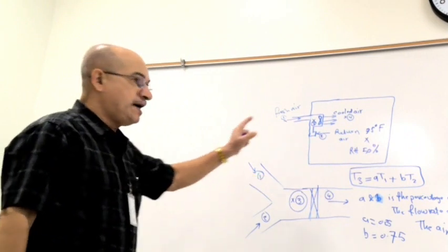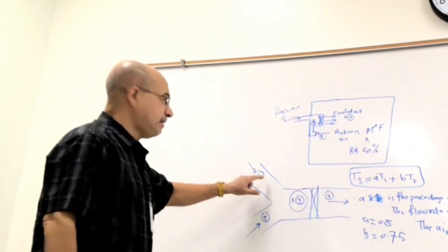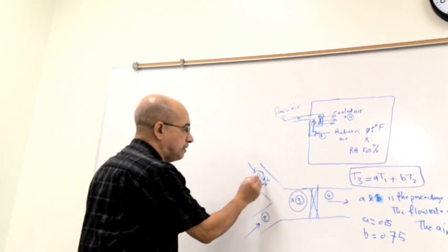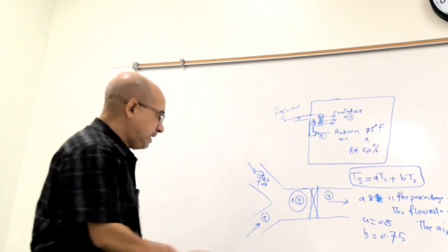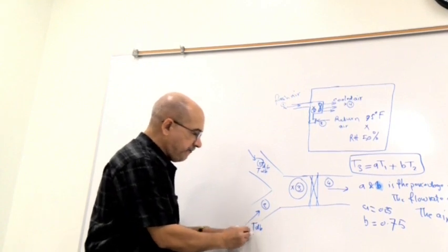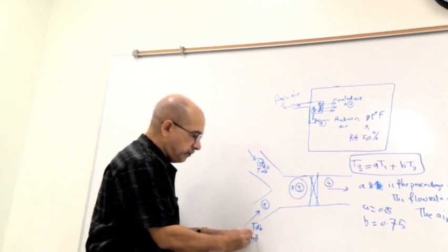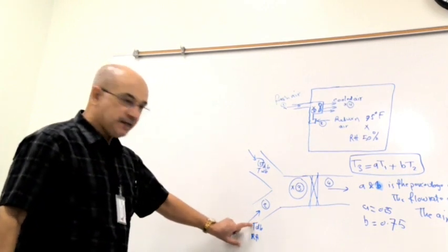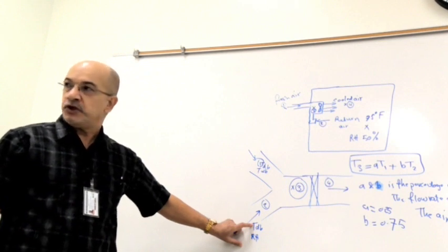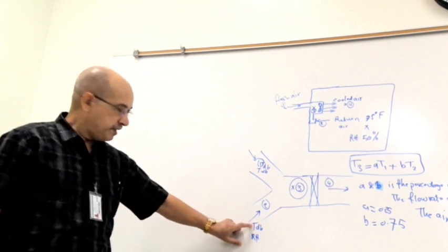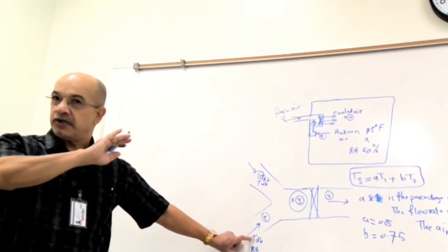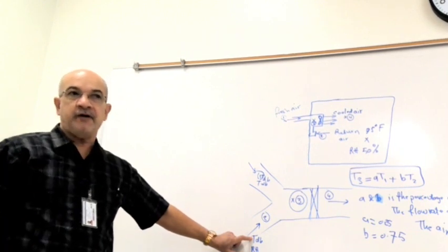So we go to the psychrometric chart. What will we do? We first find point 1. We have the dry bulb and wet bulb temperature here. For the indoor condition, we have the dry bulb temperature and the relative humidity, which, as I told you, is standard and doesn't change: 75 and 50%.